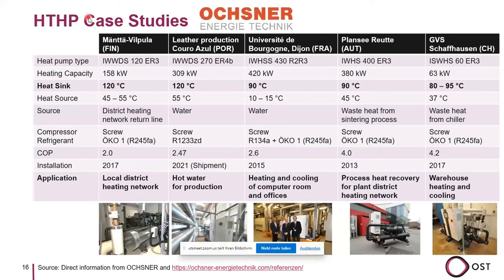So Ochsner has several case studies for high temperature heat pumps. I got them from the owner of the company. Just wanted to share this with you. So 120 degrees, 90 degrees, so a few ones are above 100 degrees. The capacity is in the several hundreds kilowatts. Here it's a local district heating network, which is 120 degrees. And then also hot water production in a leather production company in Portugal. And then some other applications in heating and cooling, process heat recovery, and so on. The screw compressor is there together with the HFC refrigerant, but also with the hydrochlorofluoroolefin.